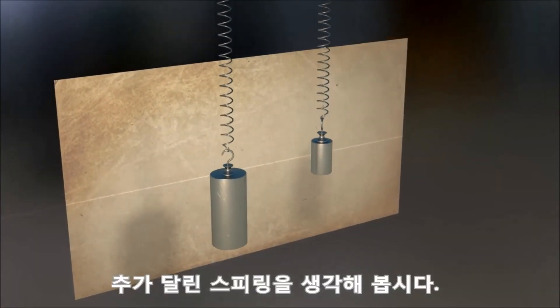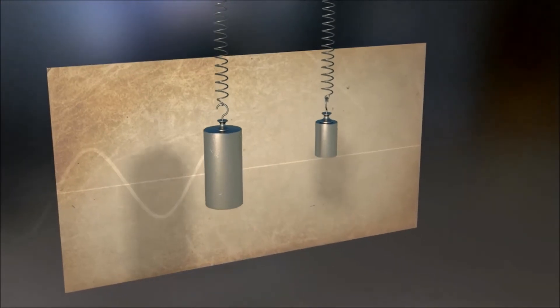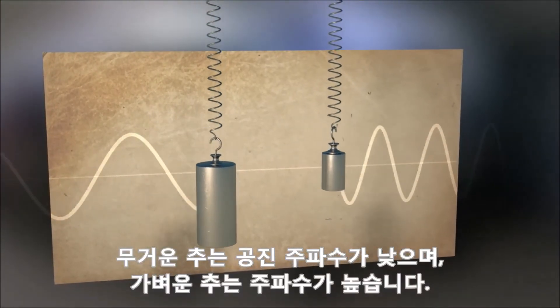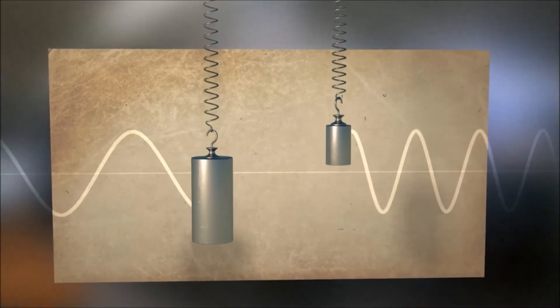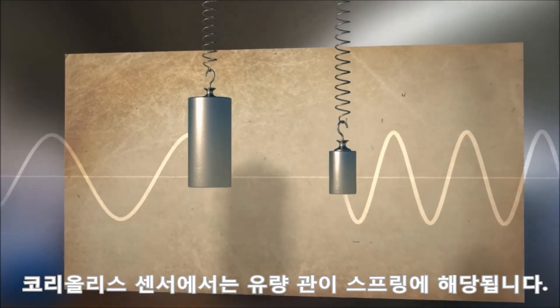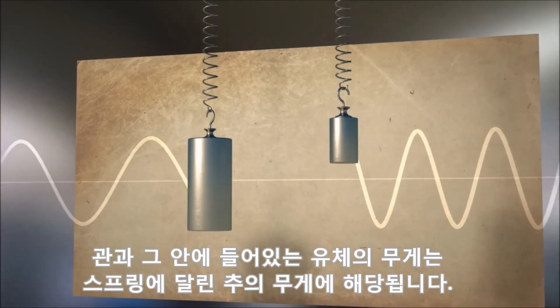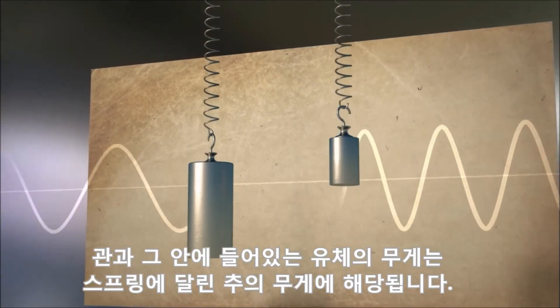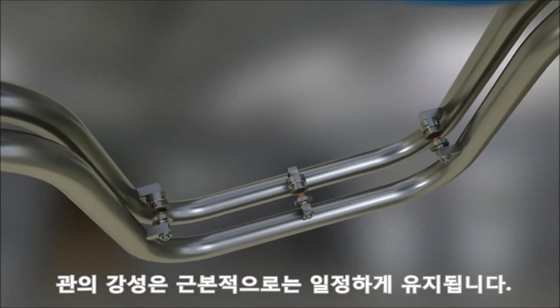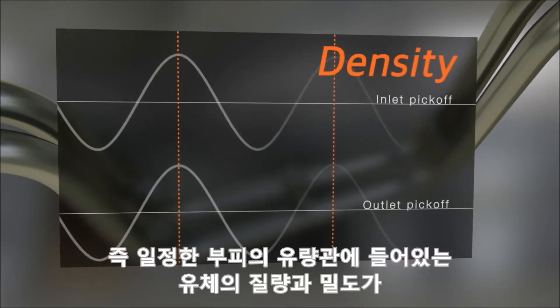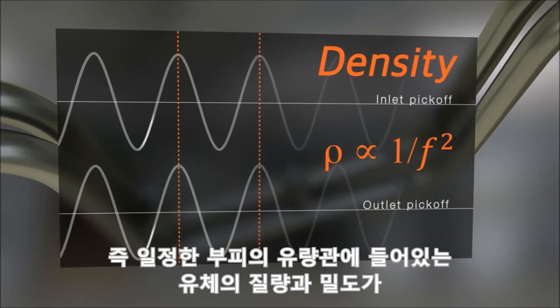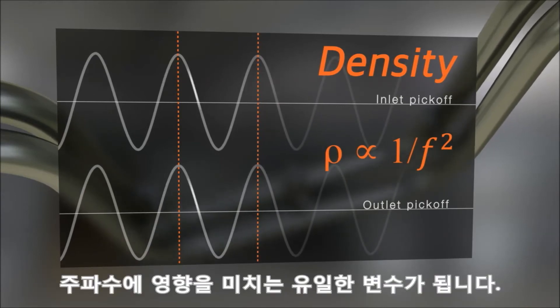Consider an example of a spring and weight system. A larger mass has a lower frequency of oscillation, while a smaller mass has a higher frequency. In the Coriolis sensor, the tubes correspond to the spring, and the mass of the tubes and the fluid they contain correspond to the weight at the end of the spring. The stiffness of the flow tubes remains essentially constant. Therefore, the mass and density of the fluid contained in the fixed volume of the flow tubes is the only variable affecting the frequency.